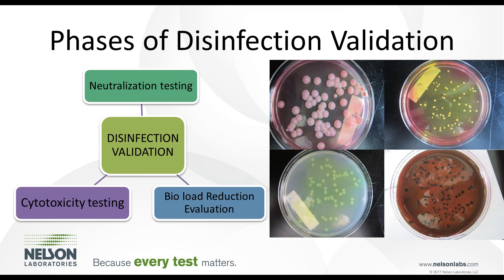The cytotoxicity testing phase is a little different from what you would do on your materials. In this cytotox testing, we're looking to make sure that the chemical used for disinfection was removed during the rinsing process to a level that is not going to cause a cytotoxic effect on the patient. So we're checking that the chemicals are removed, not evaluating material interactions.